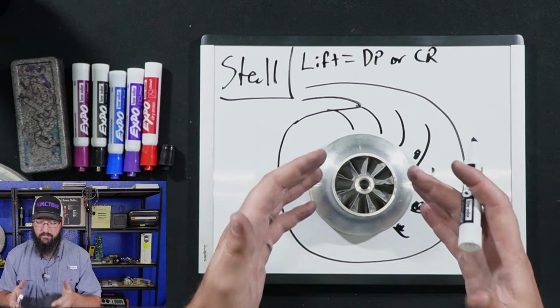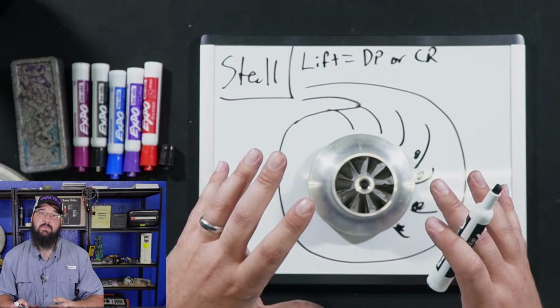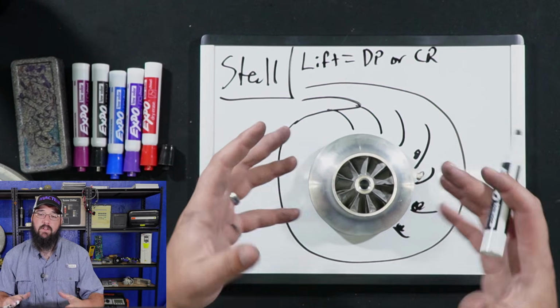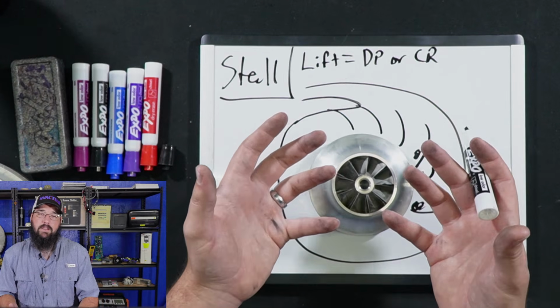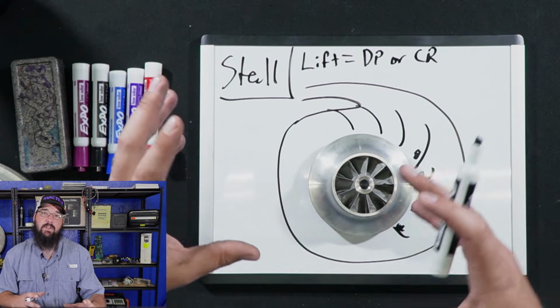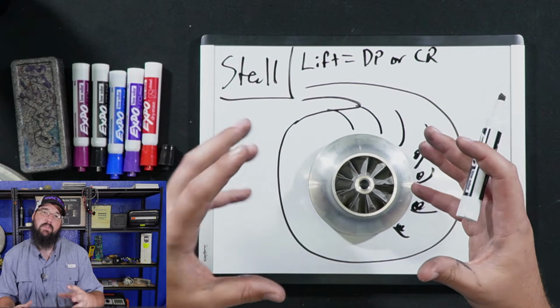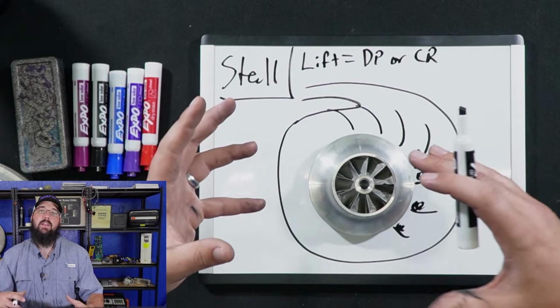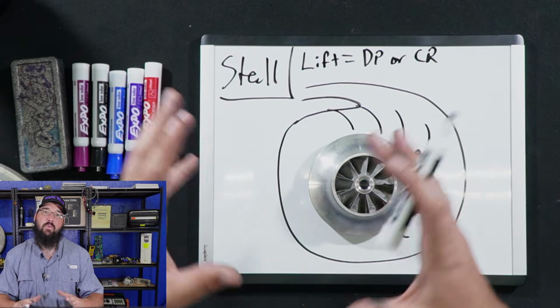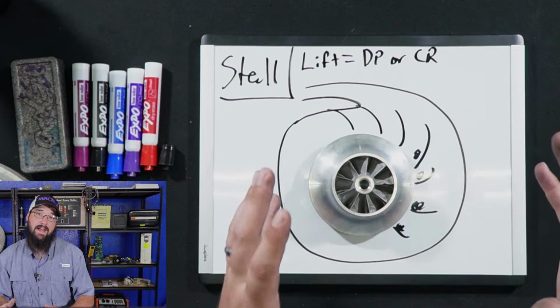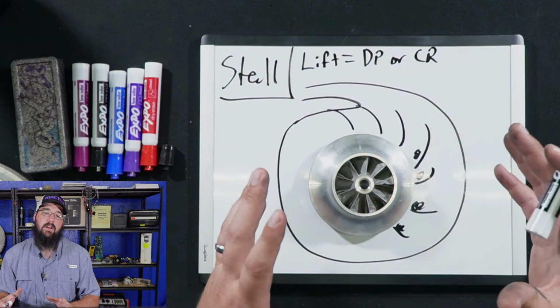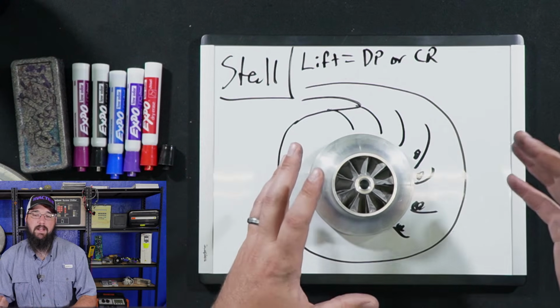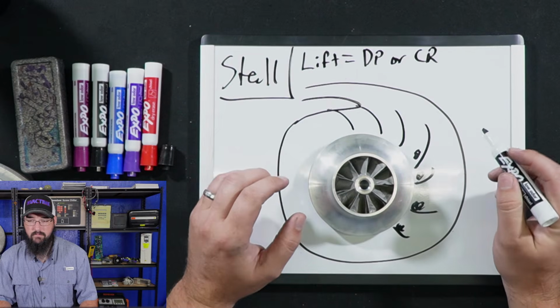Now, to do that, many times we'll close off the guide vanes. So we'll close the guide vanes a bit, and we'll balance the total flow through the compressor via closing vanes and speeding up. And the two, we can maintain the total capacity of the compressor while also overcoming a high stall condition.